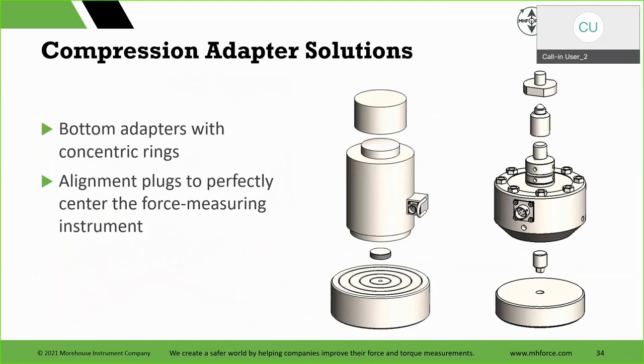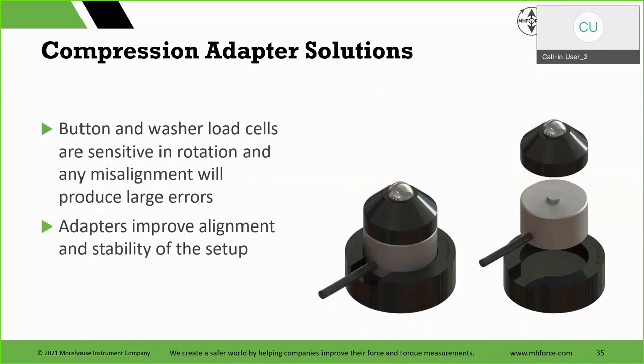How do we align this? We could align our reference cell with an alignment plug here. This is machined. The technician doesn't have to measure anything, just drop it in. The ball adapter aligns things. Here, for larger load cells, if we get into larger calibrating machines, we have an alignment plug here and, of course, our top adapter here. Then other things, compression adapter solutions. There are button load cells up close. The adapters improve alignment. You can put those in the cal machine.